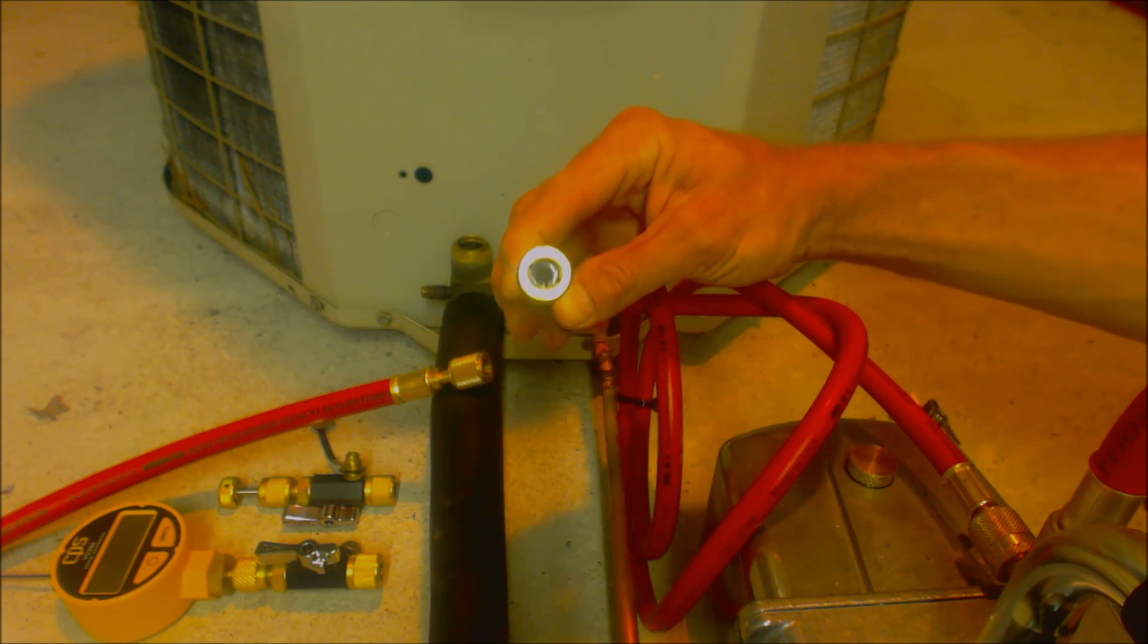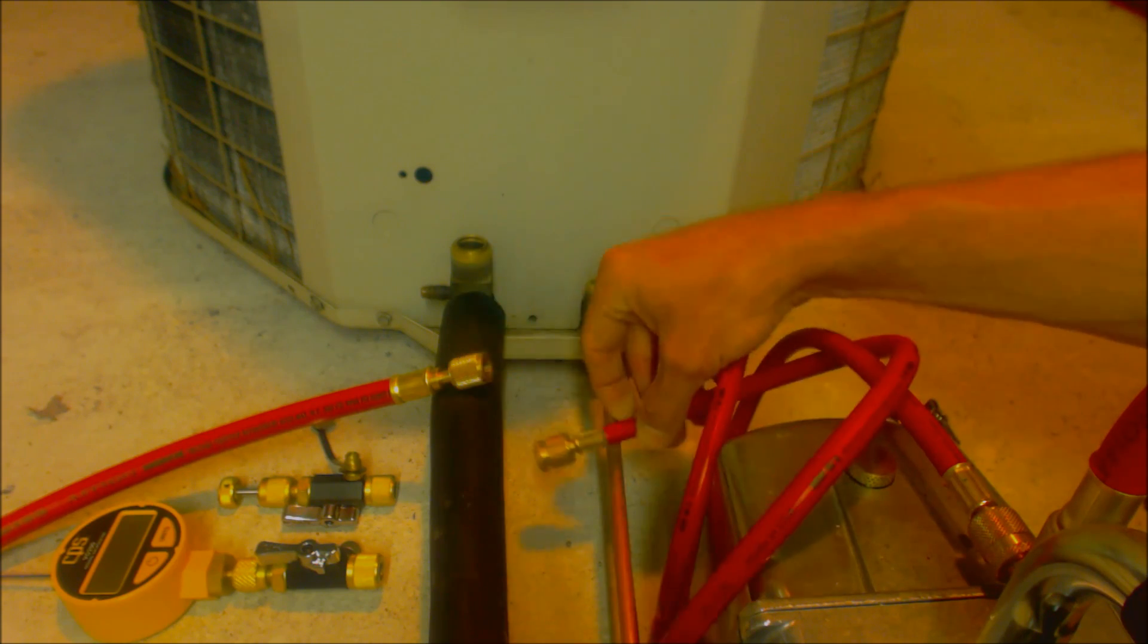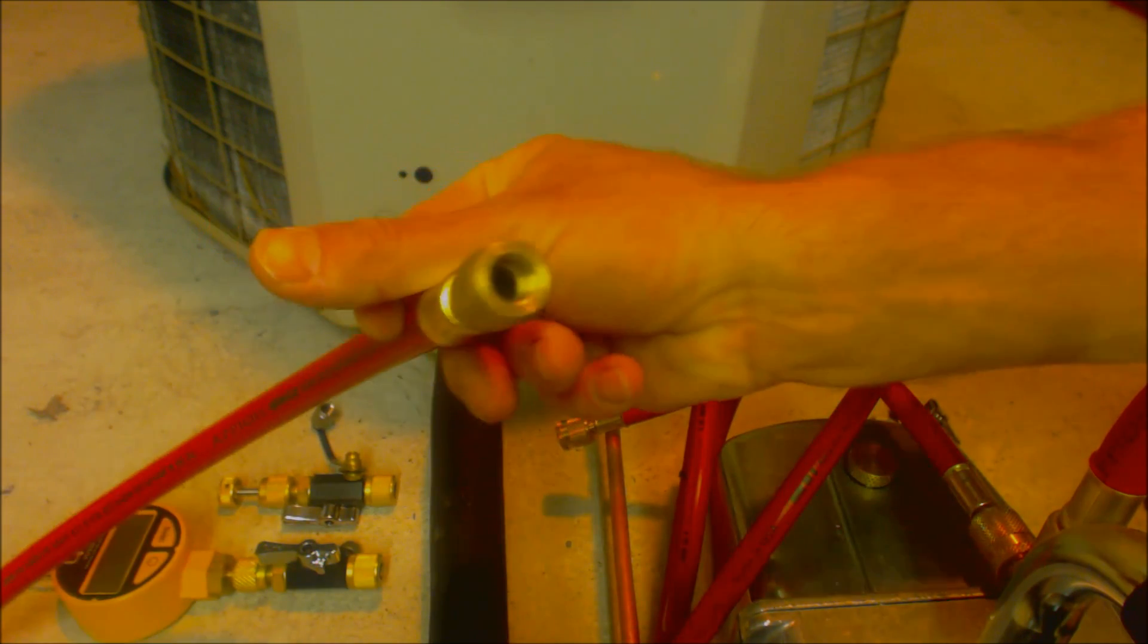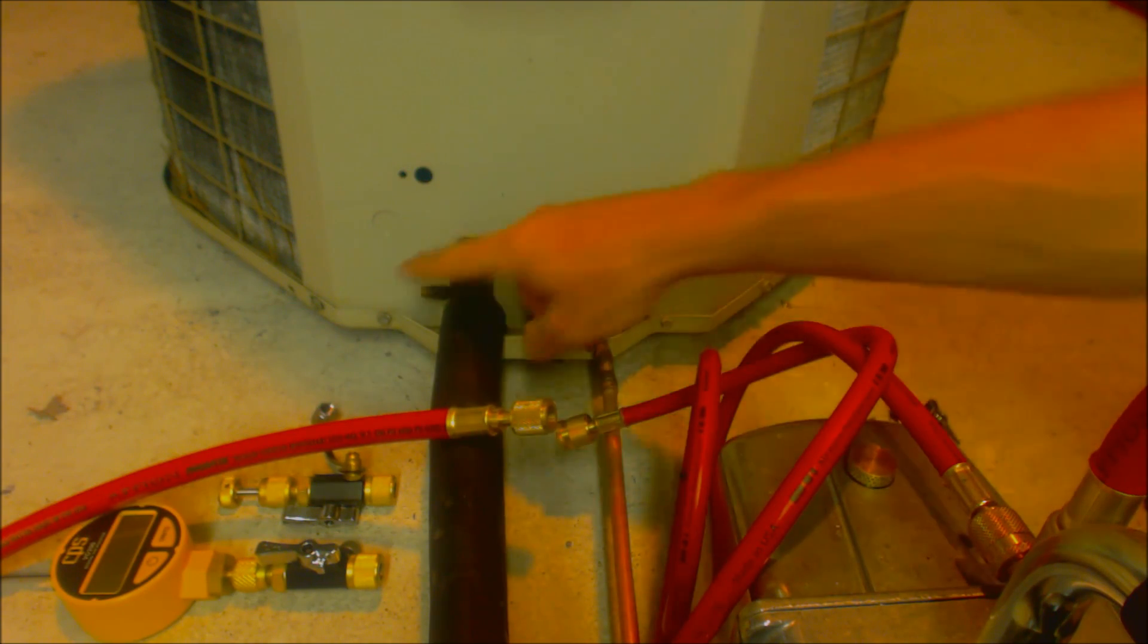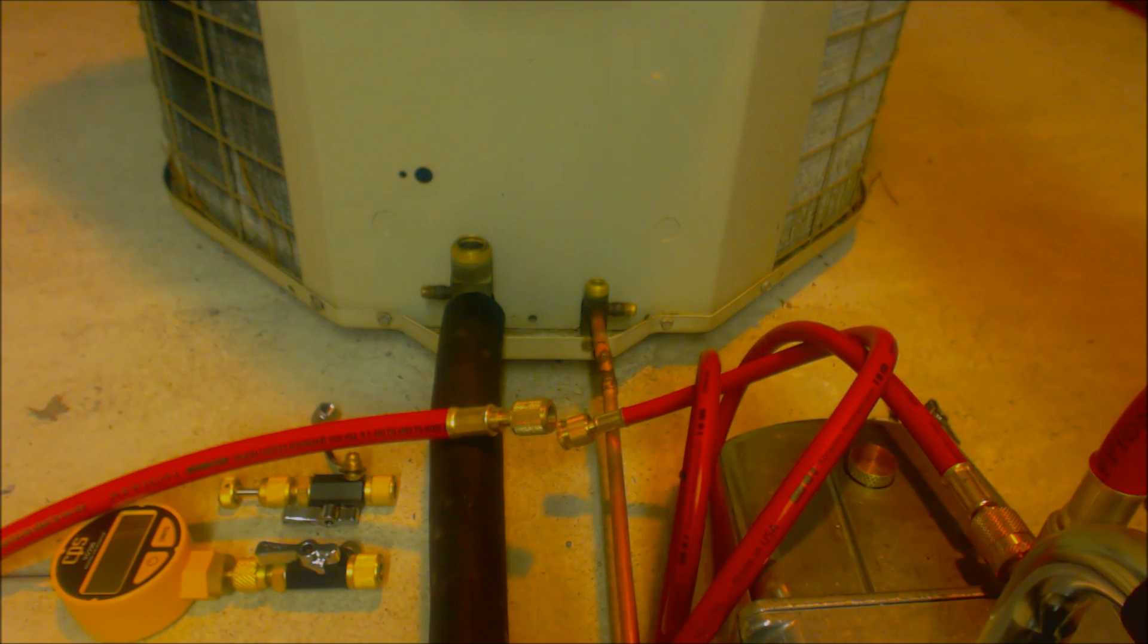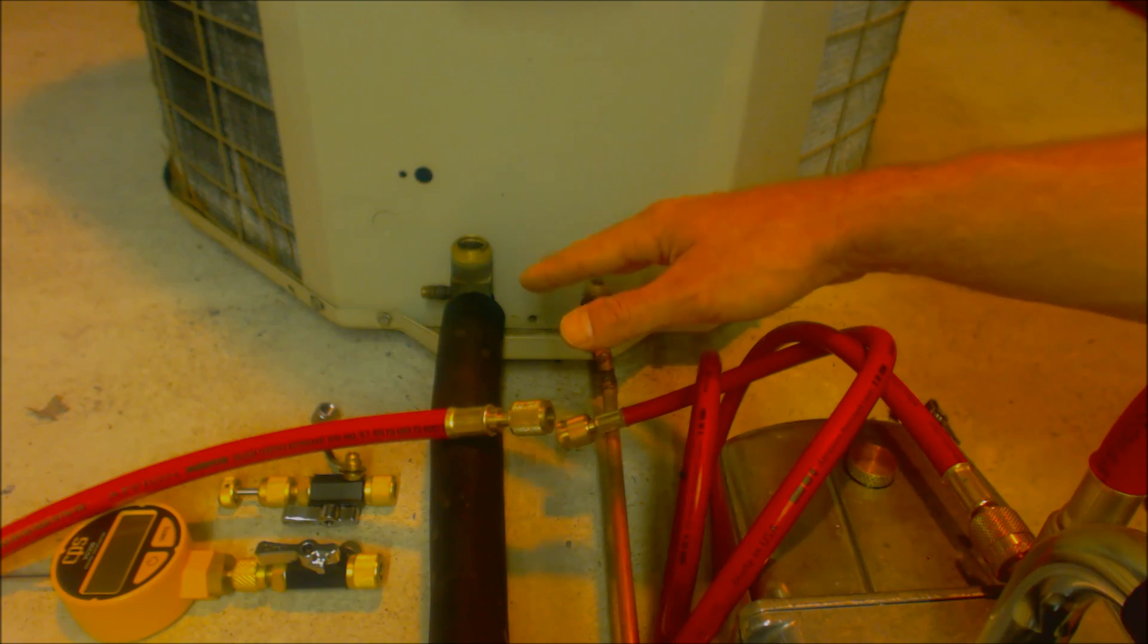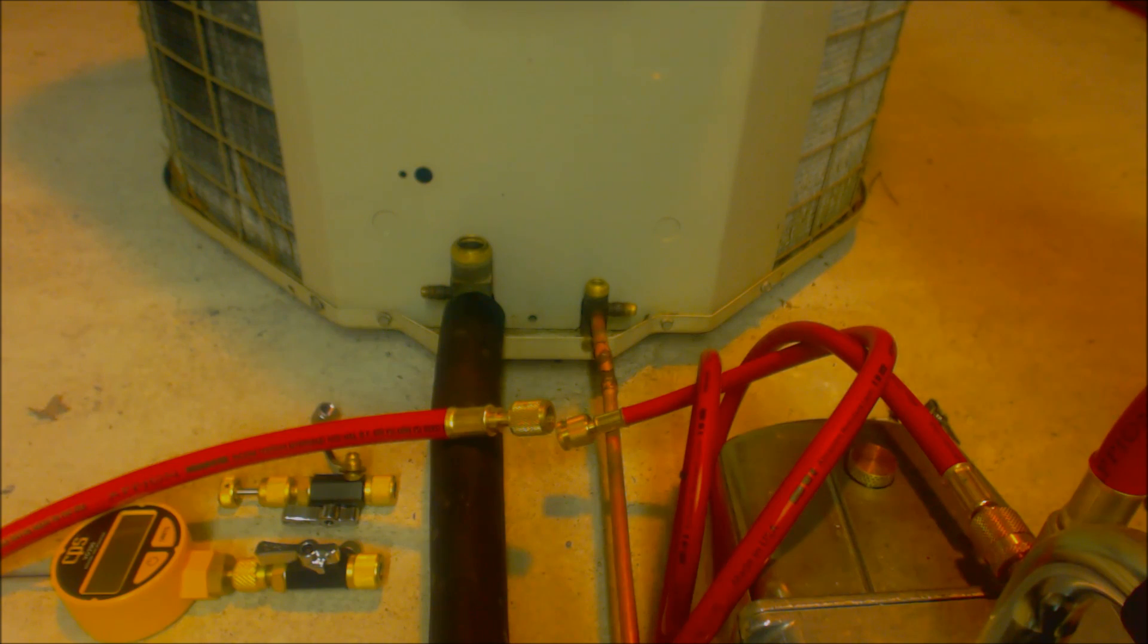Inside the hose there is no valve core depressor on this one or on this one - that would slow the flow of the vacuum. We are going to be pulling these valve cores out just to pull a more thorough vacuum. We're going to pull this vacuum down below 500 microns and it's going to hold below 500 microns. We're going to do a test for about 10 minutes just to make sure that it's holding the micron level.